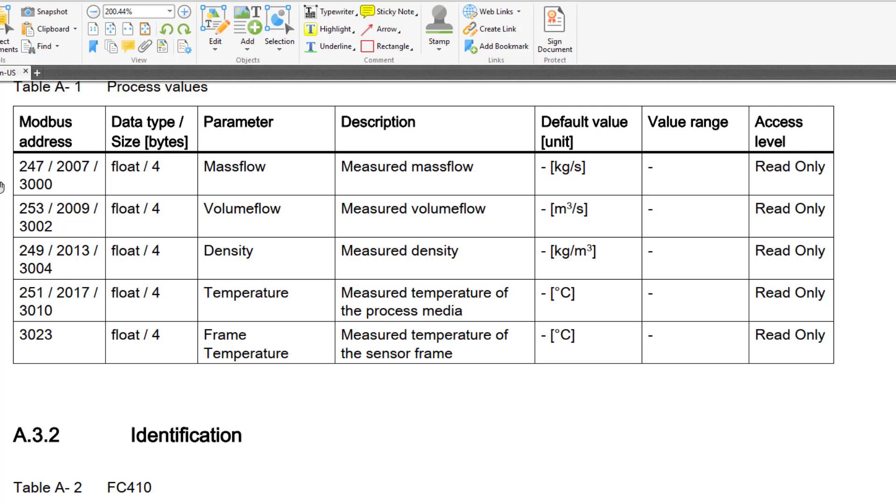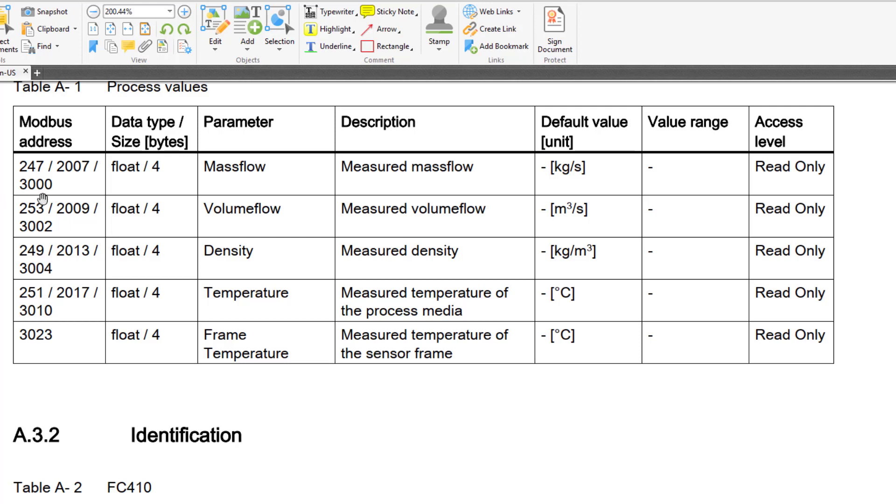So the Siemens one is always the 3000. And if you have a look here these are floating point double words. And always remember that when we are talking about Modbus we are always reading a word. So if it says quantity one that is a word. So we are looking here memory location starting 3000, 3002 is the next value, and then 3004. So that is 3 times 2 because each one of these is 2 words. So the quantity is going to be 6. The start address is 3000. Now this is where you need to be careful with Modbus because sometimes some masters are expecting that to be offset by 1. And for this example that is true. So that is 3001 for my start address and the length 6.